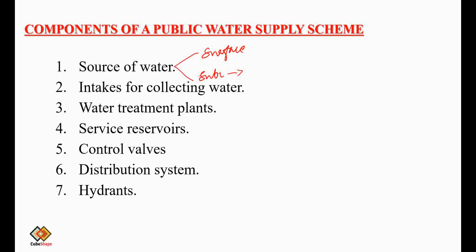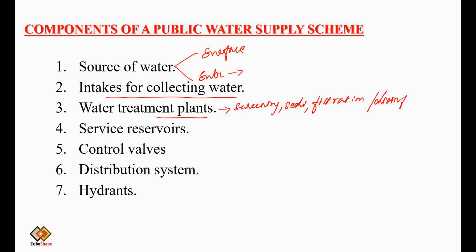The second component is the intake, for collecting the water supply — whether from a nearby vicinity or from rural places. The third component is the water treatment plant, which includes different processes such as screening, sedimentation, coagulation, filtration, and finally disinfection. Any water must be disinfected before it is supplied to consumers. For surface water, treatment methods are followed and it is disinfected before supply; if the quality of groundwater already meets requirements, it can be disinfected and directly supplied.